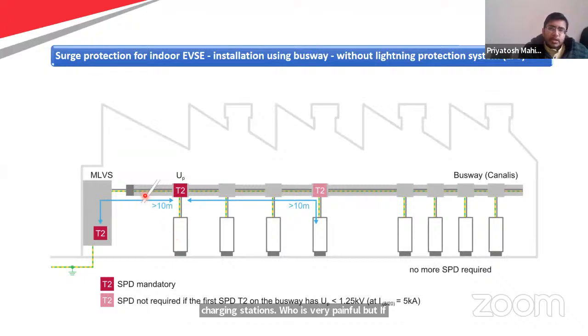But if you connect all charging stations through a busway, with SPDs placed not at the charging stations but in the busway, it automatically protects the subsequent charging stations. That's the beauty of this approach. No more SPD is required here because you've already placed your SPD in the busway, since the busway is a very conducting material and can take care of the distance. So you can straightforwardly reduce the usage of SPDs at individual charging stations.